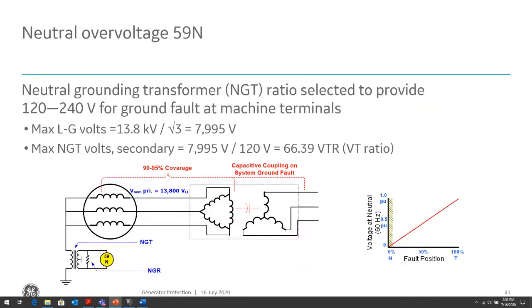So when we talk about ground faults within the generator for a high impedance grounded generator, the neutral grounding transformer is selected to provide a certain level of voltage, usually phase-to-ground voltage at the machine terminals. So basically, we can look at the generator neutral and determine if there is a ground fault. In normal operation, when there is no ground fault, the 59N should see zero voltage. As a ground fault occurs, depending on where in the winding, we're going to see high voltage. If it's at the terminals of the machine, we'll see full phase-to-ground voltage, 1 per unit. If it's close to the neutral of the machine, we'll see very low voltage.